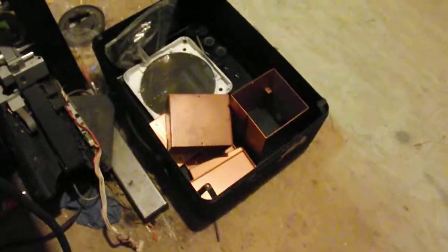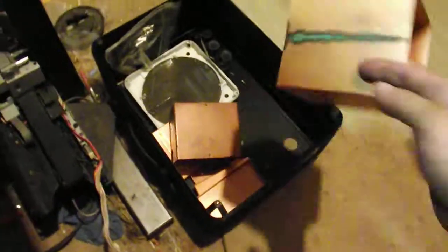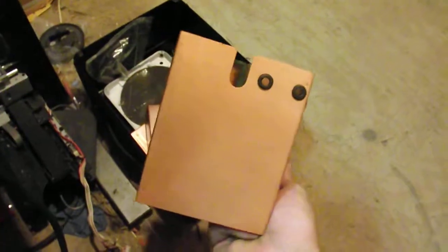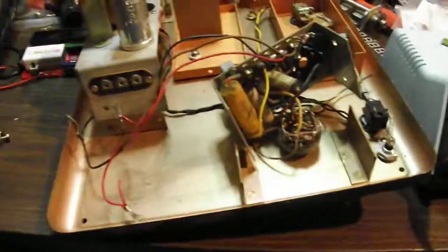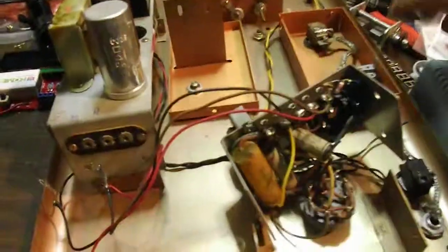And that down here on the floor is the box of screws and knobs, and every RF part in here is encased in a copper-clad metal box. So I have to put all that back together, and then I get to run the calibration procedure.